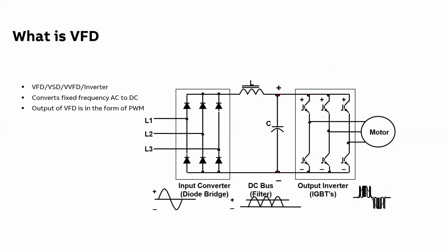Basically, a VFD converts the incoming AC signal into a DC signal. The regular supply we have is a sinusoidal 50 hertz frequency signal. This is the block diagram of a VFD. A VFD can be divided into three major parts. This is the input section, made up of a rectifier and diode bridge. Here, the incoming AC current is converted into DC current. Then this is the intermediate circuitry, where there are various capacitors and filters, where the converted DC is smoothed and we get a straight line.